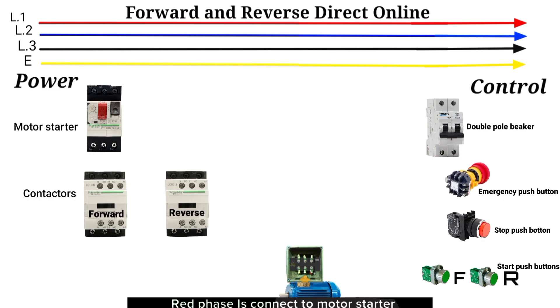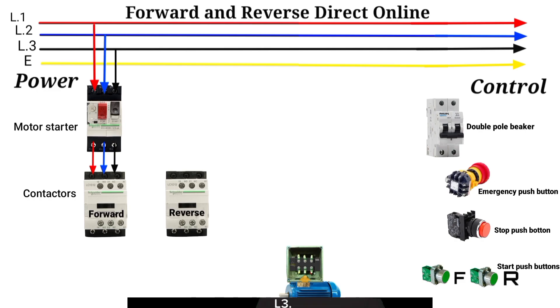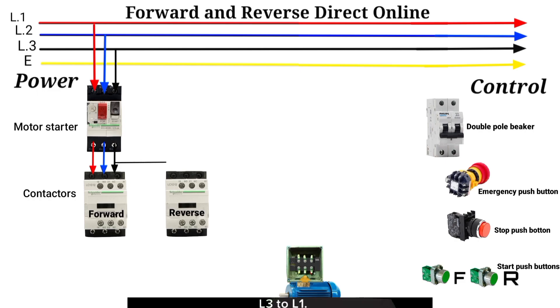Now let's start the wiring. Red phase connects to motor starter L1, blue phase to motor starter L2, black phase to motor starter L3. Motor starter output T1 connects to forward contactor input L1, T2 to forward contactor L2, and T3 to forward contactor L3.